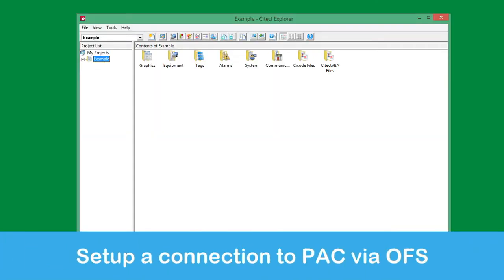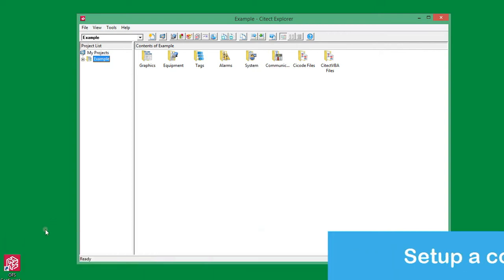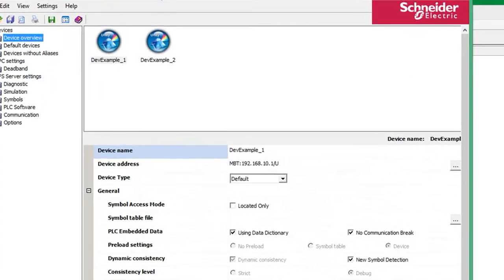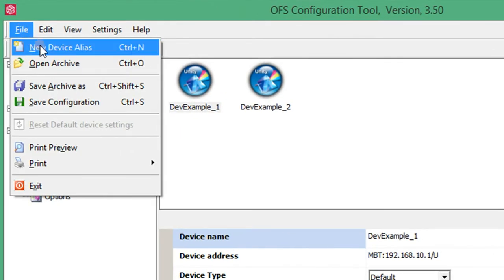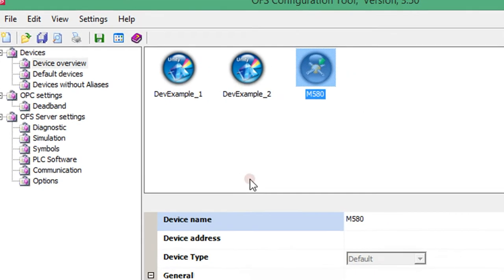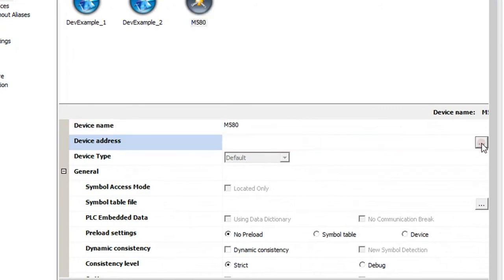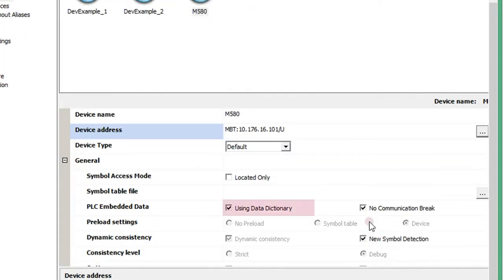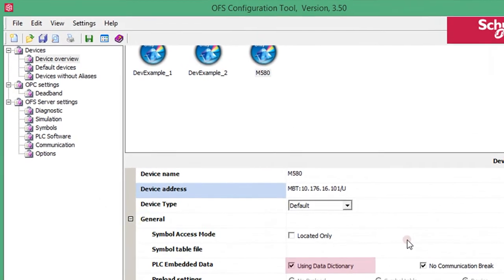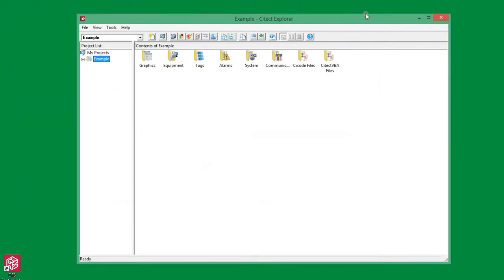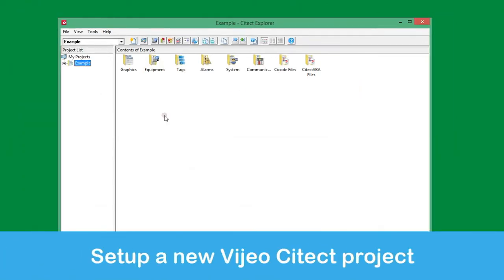The first step is to set up a connection to your PAC using OFS. Open the OFS configuration tool to set up a communication path to a new device. Then enter a name to uniquely identify your PAC and select to configure the device address. Here I will enter the IP address for an M580 device on my local network. To use the diagnostics, the data dictionary needs to be enabled both in OFS and the PAC. Then save the OFS configuration and close the tool.